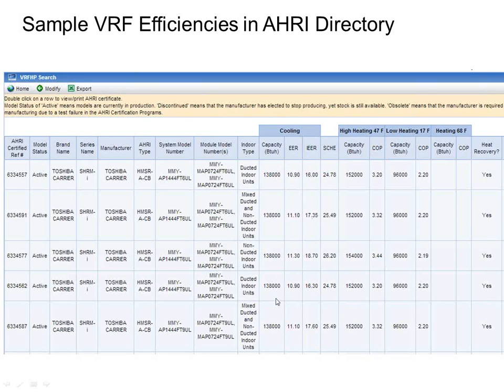The capacity is how many BTUs it's actually tested at. So yeah, this is a nominal 144,000 BTU system, but in real life it's really a 138,000 BTU system. It's just that we like to have things in nice even 6, 8, 10, 12-ton buckets, so that's why the manufacturers do that. The EER, that's our full load cooling efficiency. IEER, that was our part load. SCHE was our combined heating and cooling efficiency when I have zones mixed together that need opposite things. Then I got my heating capacity, in this case 152,000 BTUs.